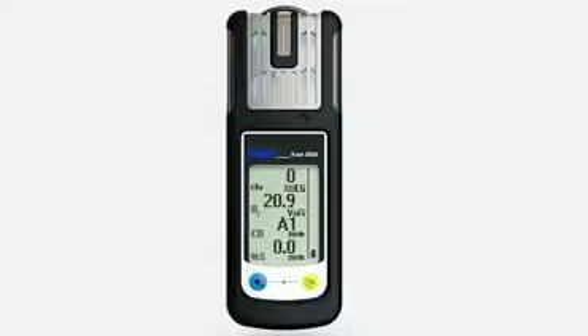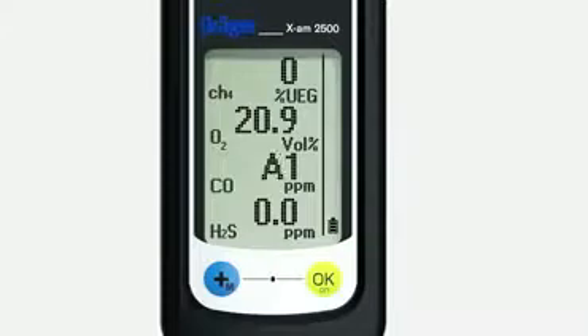The A1 alarm sounds if the concentration is higher than normal but doesn't yet constitute an acute hazard. The audible, visual and vibration alarms are all activated periodically. A1 alternates in the display with the gas concentration. An A1 alarm can be acknowledged by pressing the OK key. The alarm automatically stops as soon as the concentration drops below the defined threshold.